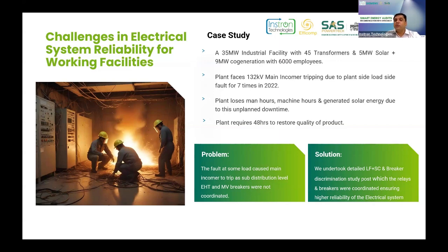The plant in the year 2022 faced around 7 trippings of their main incomer, that is the 132 kV substation incomer, due to plant side load faults. The effect was that the plant lost man hours and machine hours. They also lost the generated solar energy due to this unplanned downtime. The worst part is the plant required 48 hours to restore the quality of their product. So you can imagine the substandard production must have been a waste. Please try to account for the carbon emission losses of these 48 hours whenever we are calculating the loss because of downtime of electrical infrastructure.